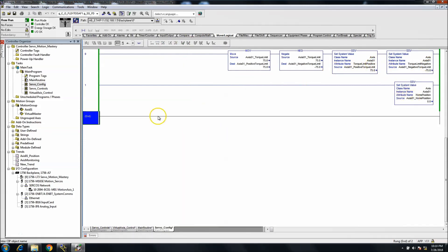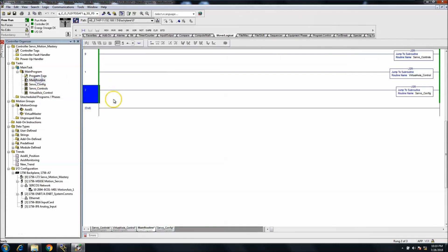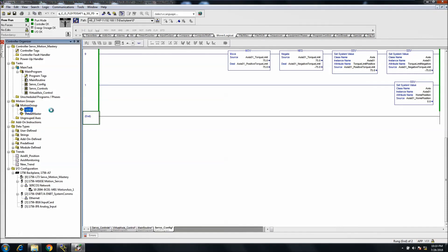We've now written a couple of things in our configuration. If you're going to write out a big configuration, I would suggest keeping this as a one-time write rather than a constant jump-to-subroutine. You can have it write just one time, and when it's done writing, just disable it - have it latch and then come back and unlatch it. This is useful if you just want to set hard-coded numbers without having to constantly open up the properties.